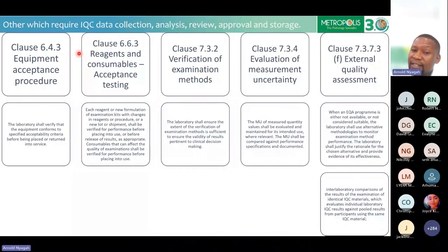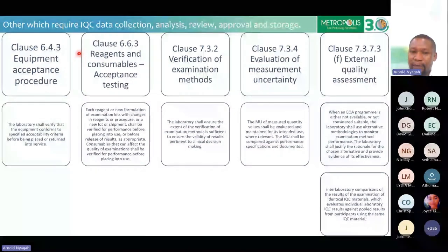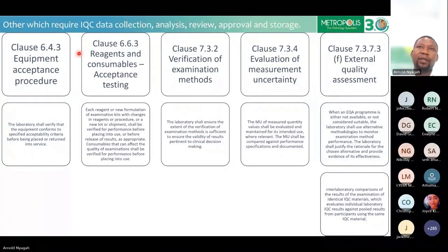On measurement of uncertainty, you need to review your measurement of uncertainty at specified intervals, and this also has to be documented. Like you've seen, the Unity real-time has really assisted us in calculating the measurement of uncertainty, whether you are using the standard expanded measurement uncertainty or using it together with your EQA provider. All of this is available to measure the measurement uncertainty.